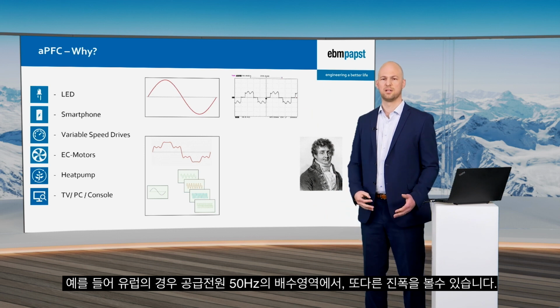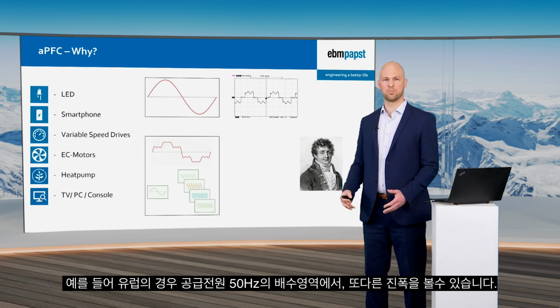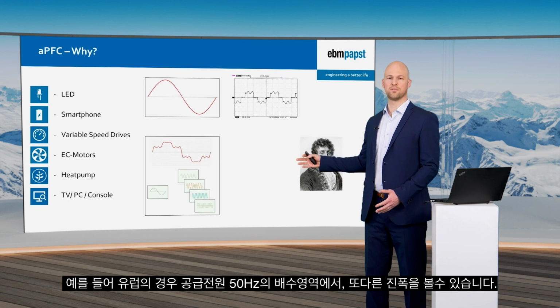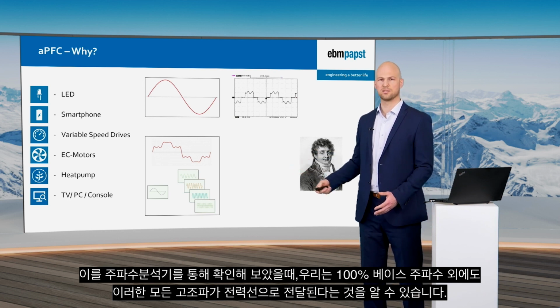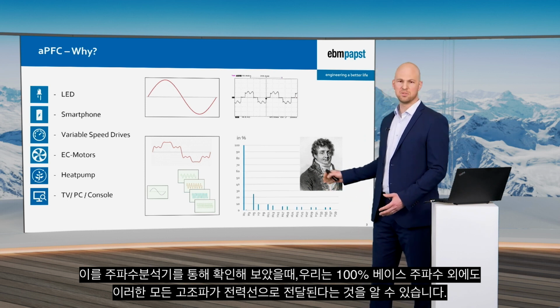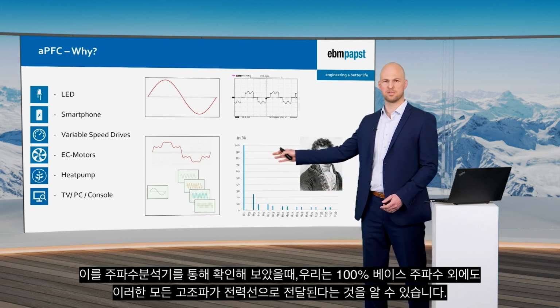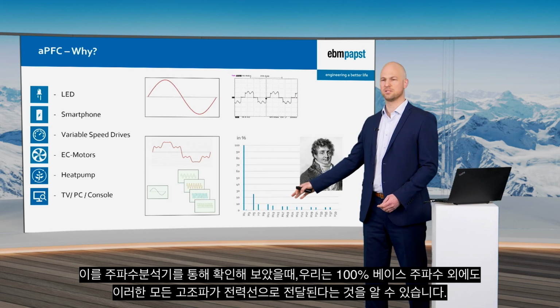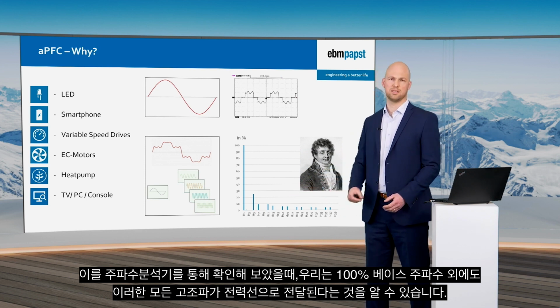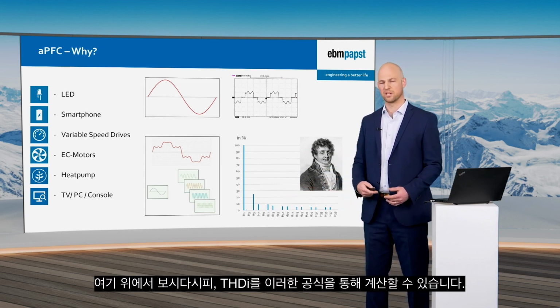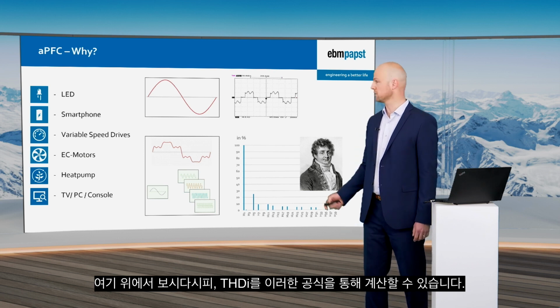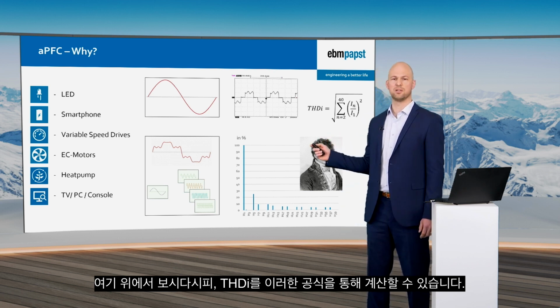So, for example, the 50 Hertz frequency in Europe will produce multiples of 50 Hertz in the supply grid with different amplitudes. Looking at the frequency spectrum, besides the 100% base frequency, we also transmit all these harmonics along the power lines. We can calculate a so-called THDI, and the formula for this can be seen up here.